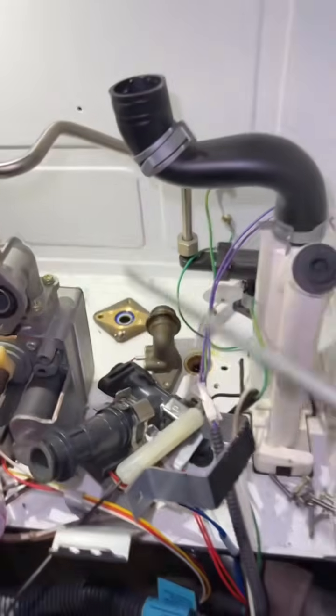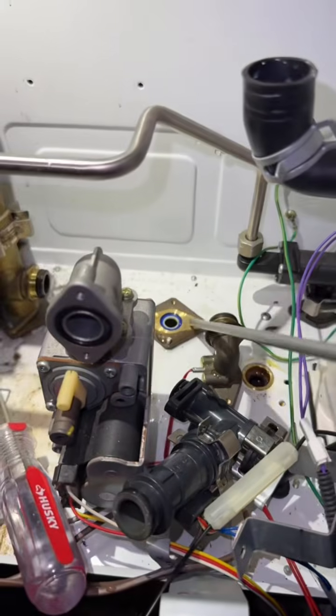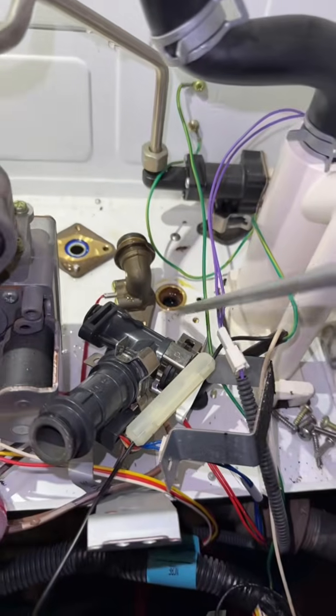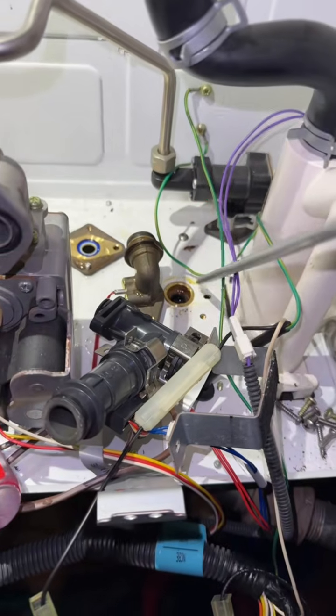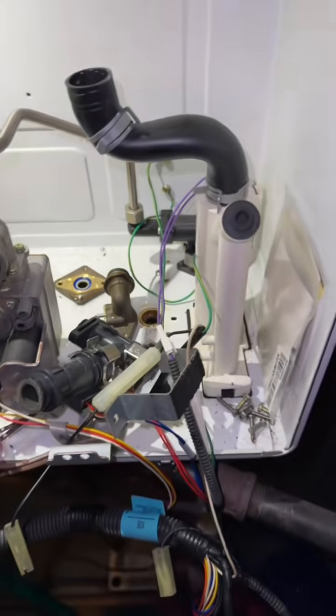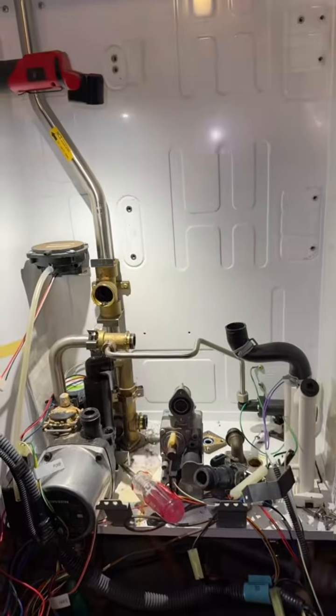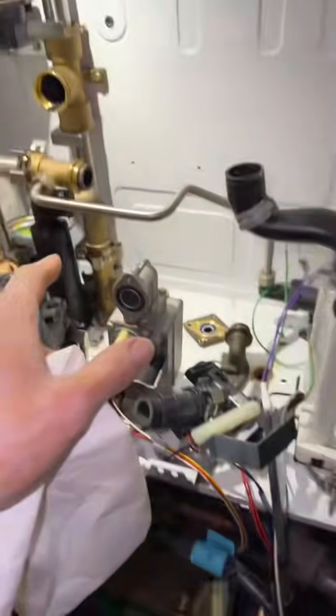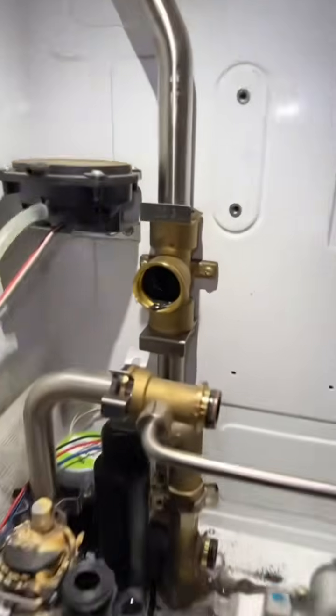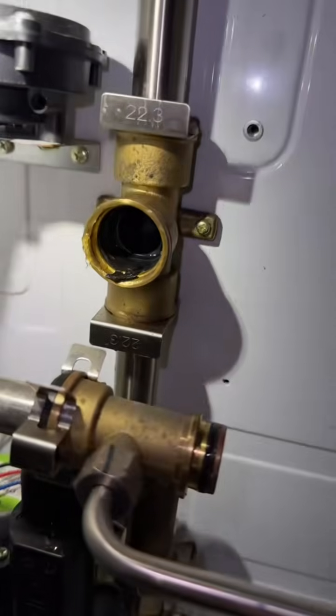That flat plate sucks. You have to take these screws off from the bottom, take these screws off from the top, take another screws off from the bottom, undo those two fittings. Ugh, it's wild. But replacing those 3 items in the boiler, and then the flue pipe, it took me about 5 hours. You might be able to do it in 3 if you do it a bunch. I'd still price it for 5, just in case.